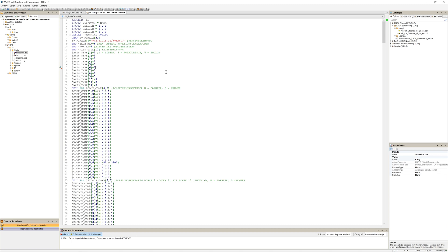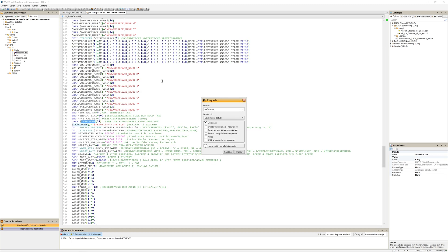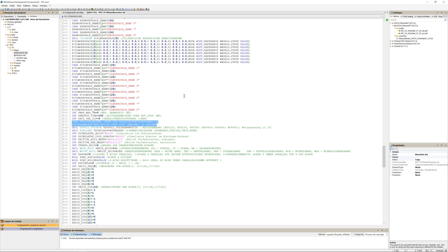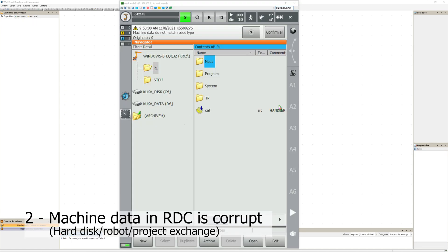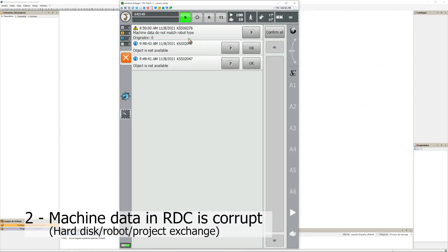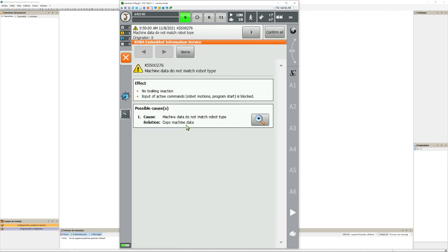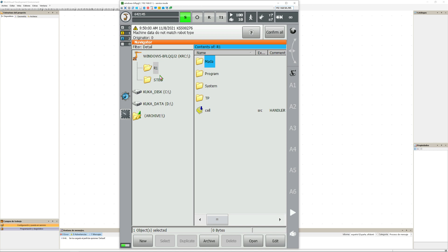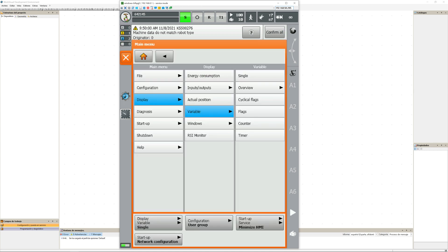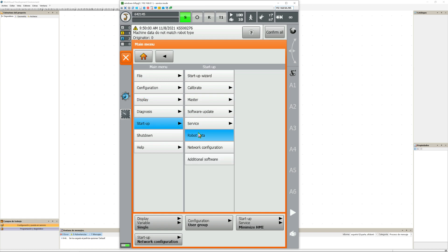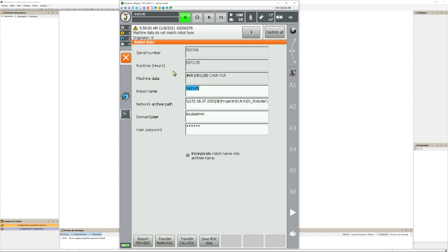The variable travel name can only be changed when you load the project in WorkVisual to the controller. Another error that you might encounter is the machine data is wrong. This can be caused by some sort of corruption, sometimes during changing hard drives or even projects in WorkVisual, or if you exchange one robot and use the same controller to move another robot.